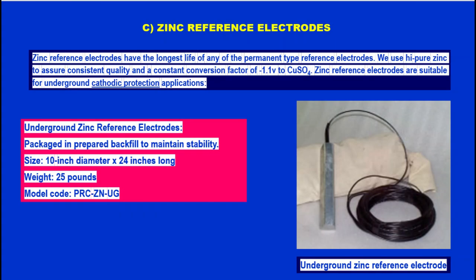The next type of electrode is Zinc Reference Electrodes, which have the longest life of any permanent type reference electrode. High purity zinc is used to assure consistent quality and a constant conversion factor of minus 1.1 volt to copper sulfate. Zinc reference electrodes are suitable for underground cathodic protection applications. Underground zinc reference electrodes are packaged in prepared backfill to maintain stability. Size: 10-inch diameter, 24 inches long, weight 25 pounds. Model code: PRC-ZN-UG.